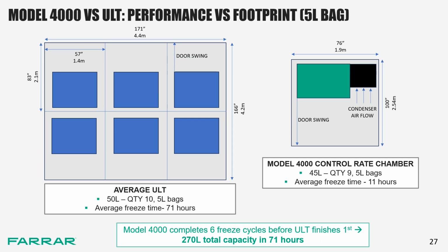This equates to about 270 liters of freezing capacity in roughly 3 days versus 50 liters using a ULT. To match that, you'd need 6 ULTs taking up roughly 197 square feet (18 square meters) of floor space, compared to a single Model 4000 at about 52 square feet (4.9 square meters)—almost 4 times more floor space needed for the ULTs to freeze the same amount of material.